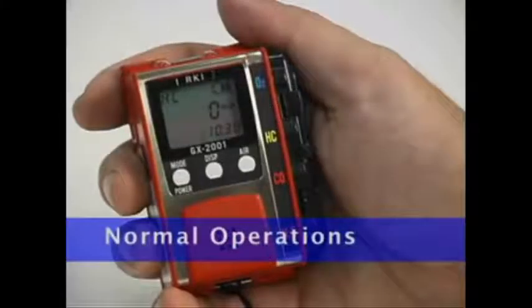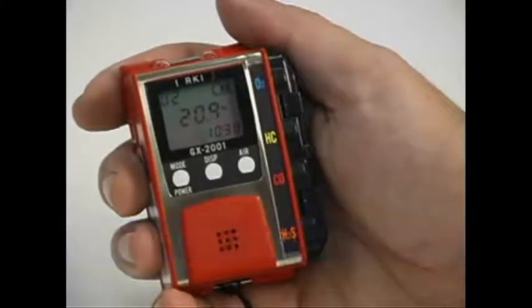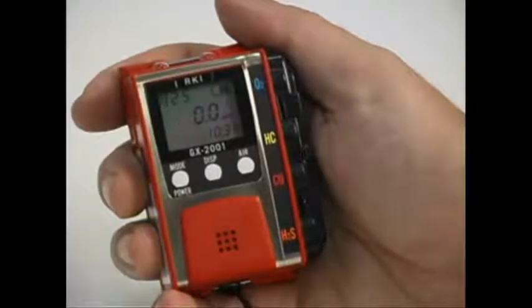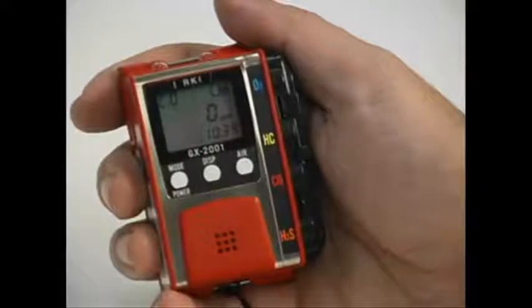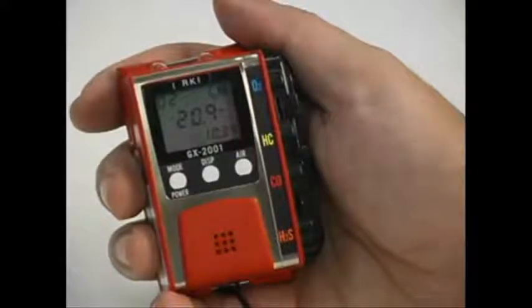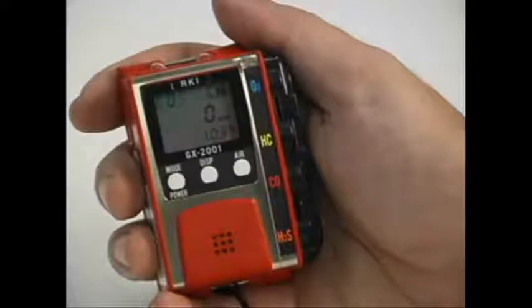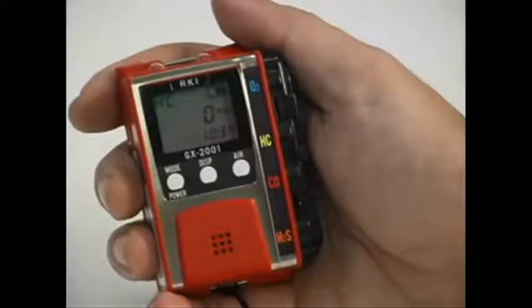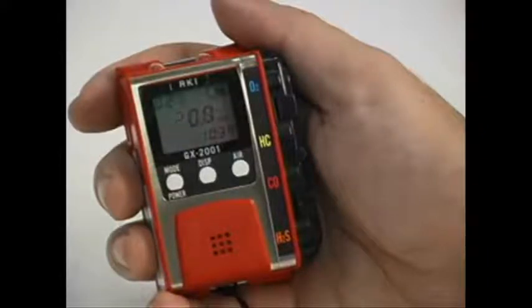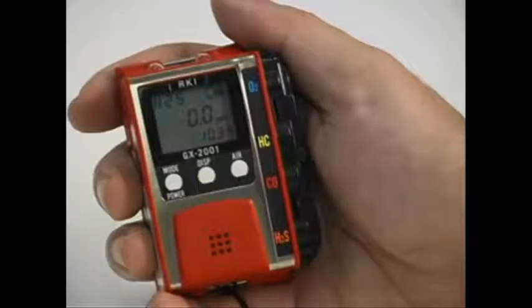In the GX-2001's normal operation or measuring mode, the battery level, time, and gas concentrations are displayed on the LCD. The GX-2001 cycles through the 4 target gases, starting with oxygen, then H2S, CO, and hydrocarbons. Oxygen is displayed as a volume percentage. H2S and CO are displayed as parts per million, or ppm, and the combustible gases are displayed as a percentage of the lower explosive limit, or percent LEL.